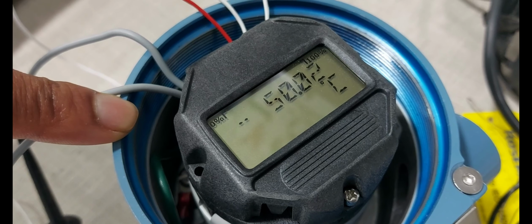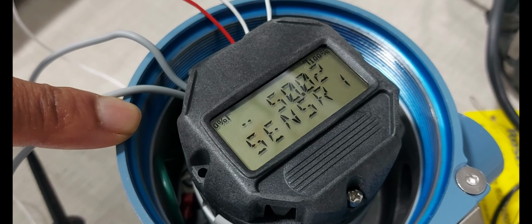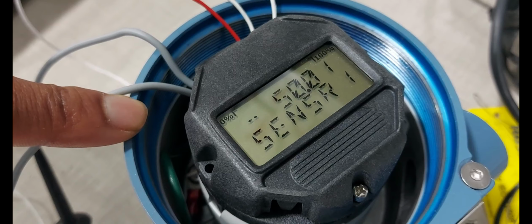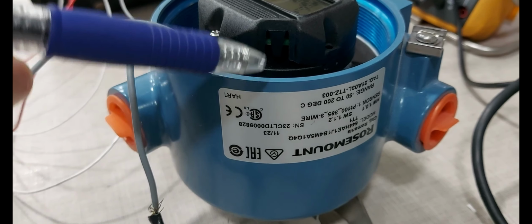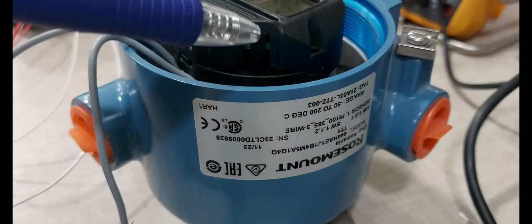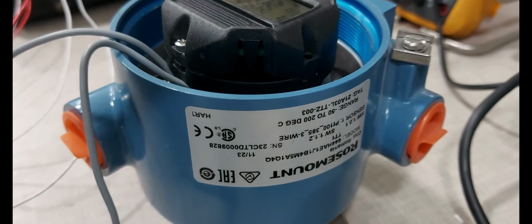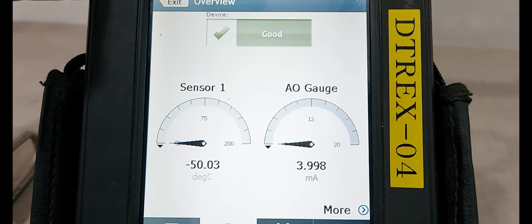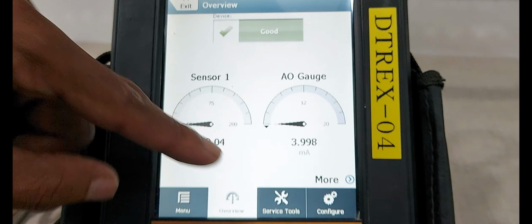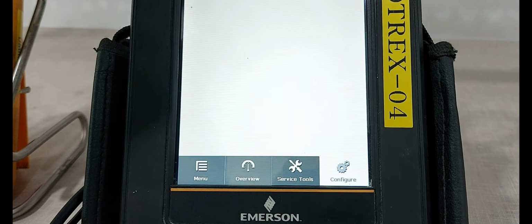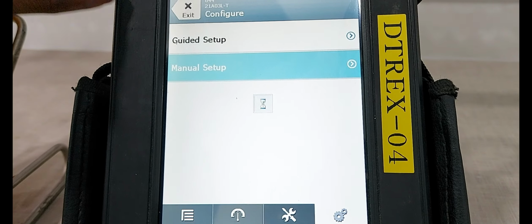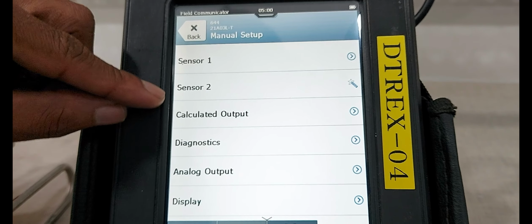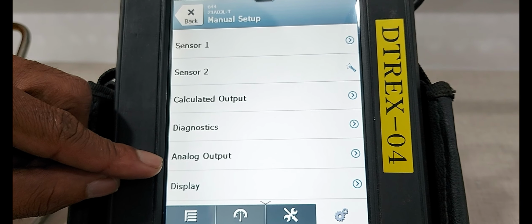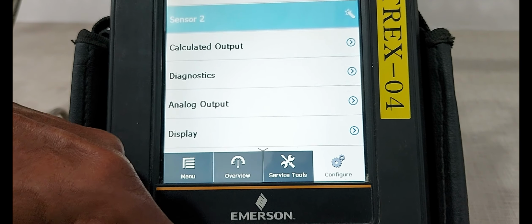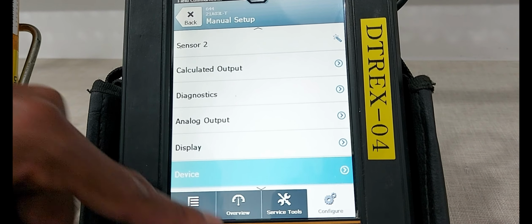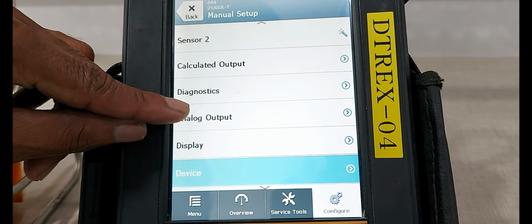Rosemount 644 HAE model temperature transmitter calibration procedure. Process variable LRV changing procedure. I will explain how to change the LRV and URV, which menu we can edit for the LRV and URV. This is the overview menu. First we are changing the configuration. Select it, configuration, and select the manual setup. Sensor 1, sensor 2, calculation output, analysis service, analog output, display settings, device setup. Okay, first we are selecting analog output functions.